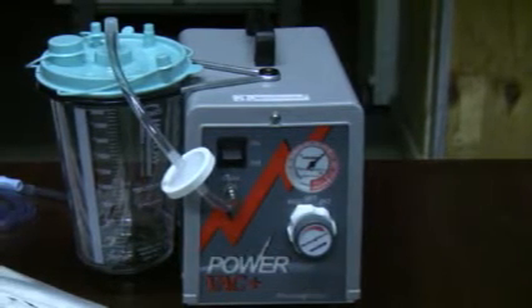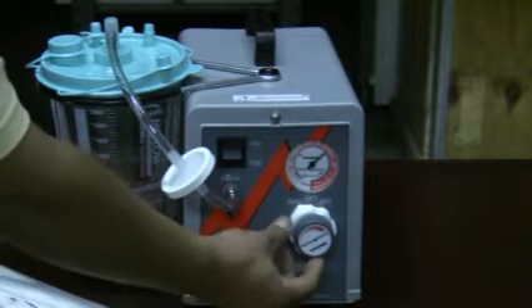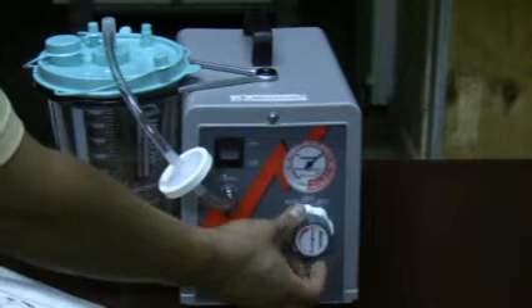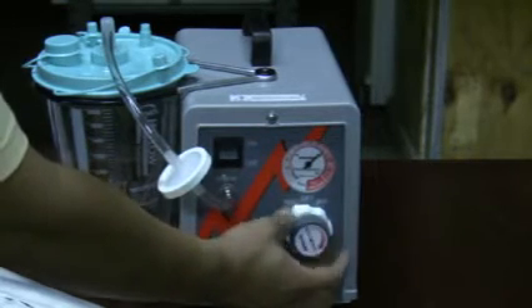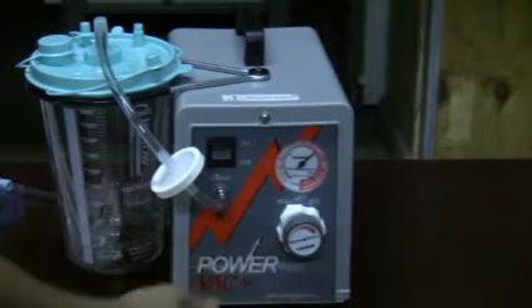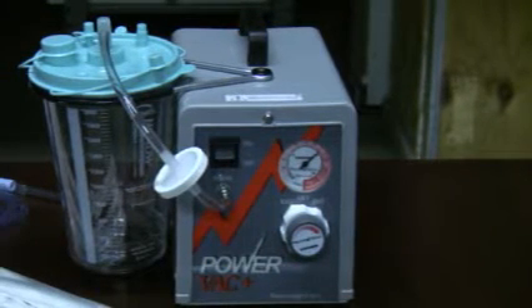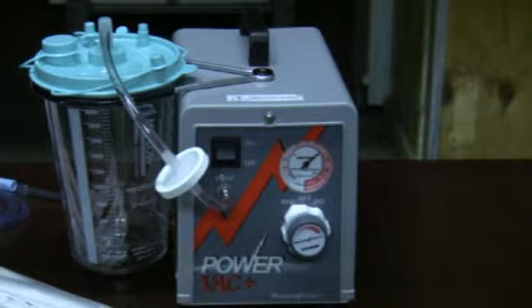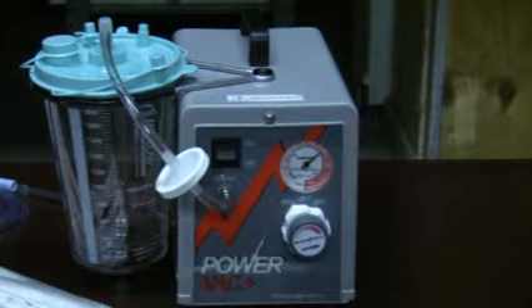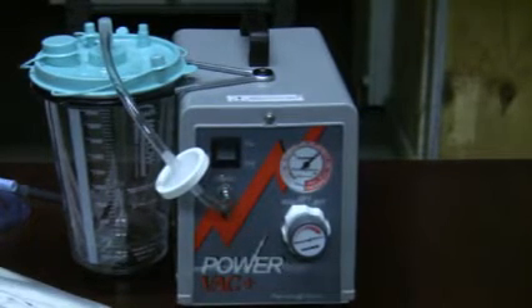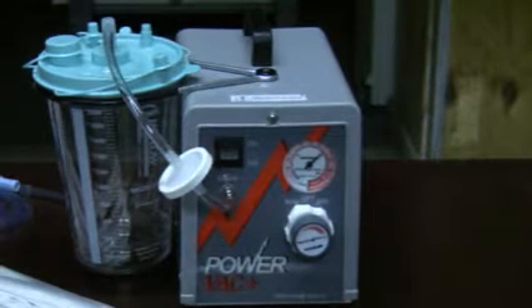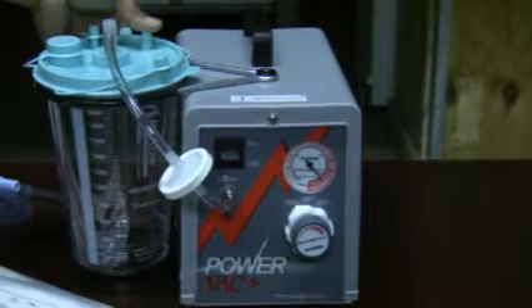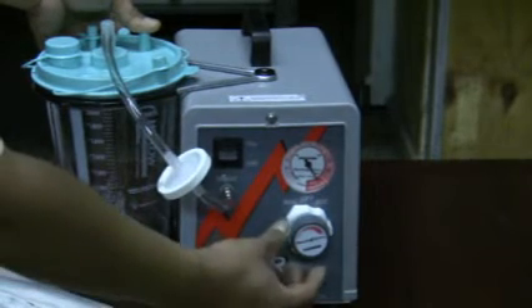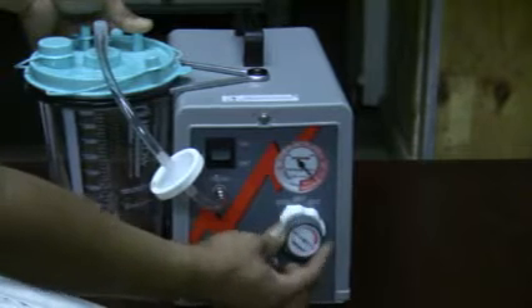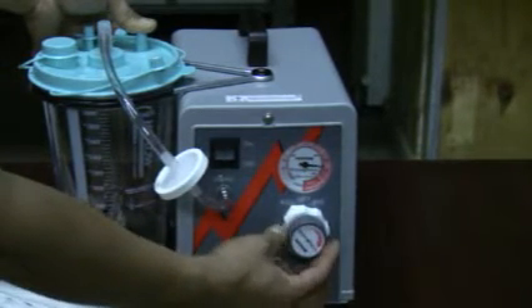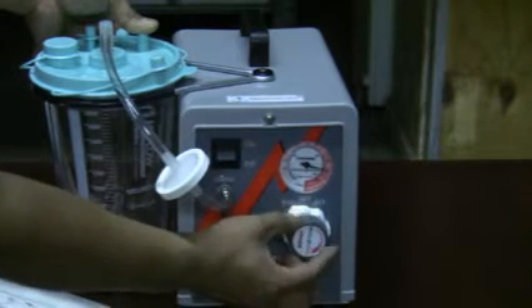If you were trying to make any pressure adjustments with your vacuum pressure control knob by turning counterclockwise or clockwise, you will not be able to see the difference of change in vacuum pressure because of the vacuum leak. So while selecting your vacuum pressure, you should cap off or kink your tubing if connected, and then during this time use your pressure gauge selector to decrease or increase your suction pressure as needed.